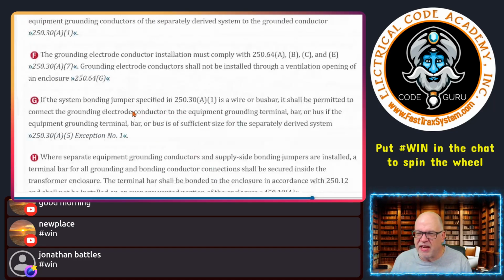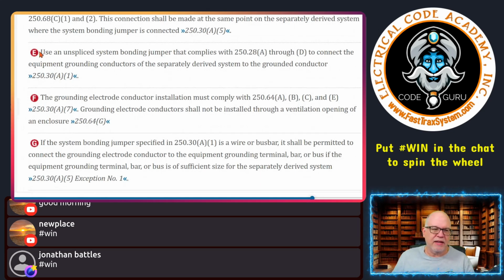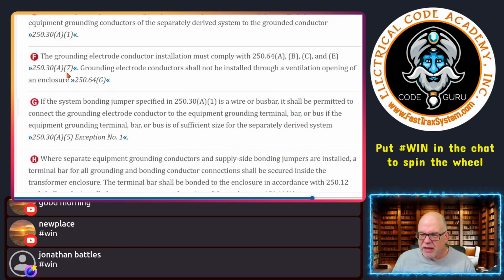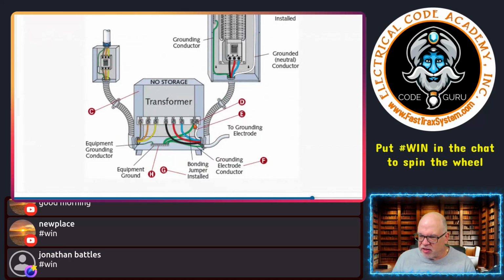That was D. Now E, in this separately derived system we're doing, is an unspliced system bonding jumper that complies with 250.28A through D. Again, that's going to tell you the material you can use, and it gives you directions on sizing, which ultimately, at the end of the day, is going to send you to 250.102C1. But all that starts there when it comes to sizing. And so that is this conductor right here.